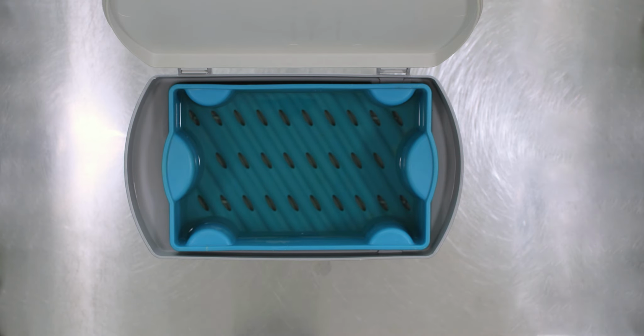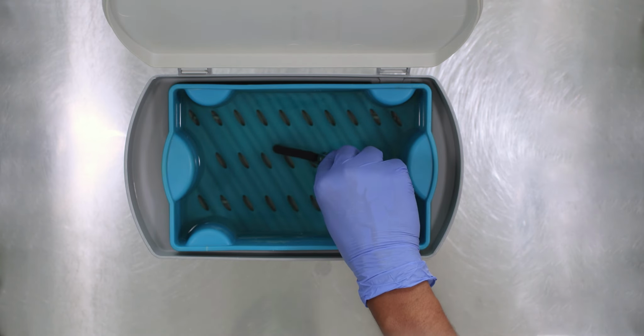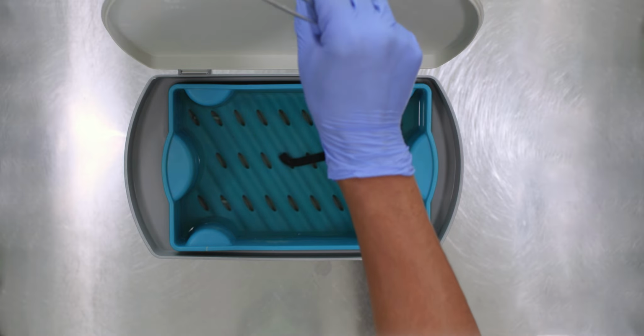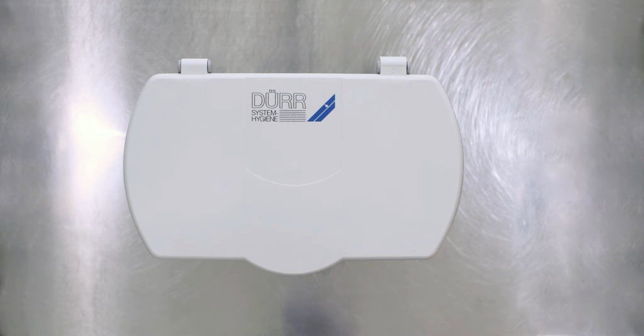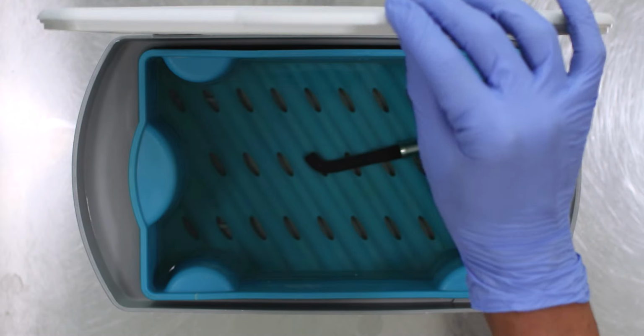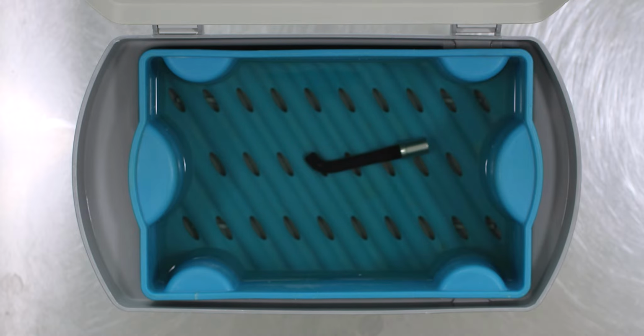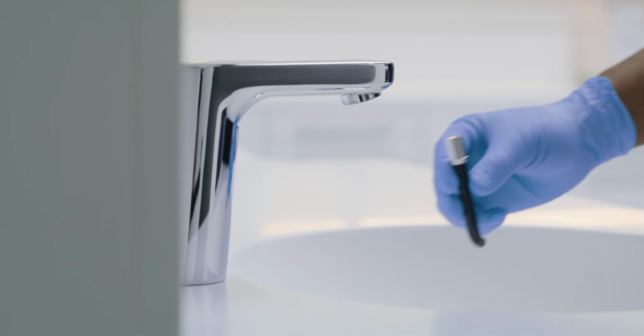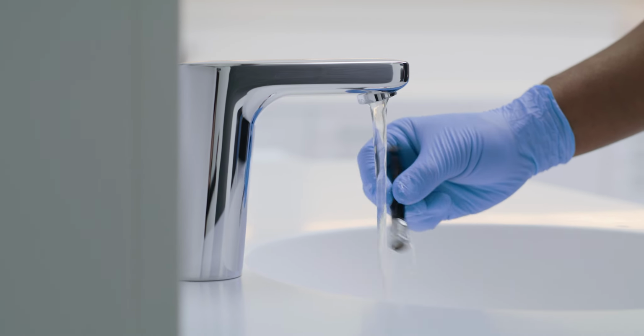For manual cleaning, place the light guide in an instrument cleaning solution for 15 minutes. Make sure the light guide is sufficiently immersed in the cleaning solution. After the cleaning process, remove the light guide from the solution and thoroughly rinse it under running water for at least 10 seconds.